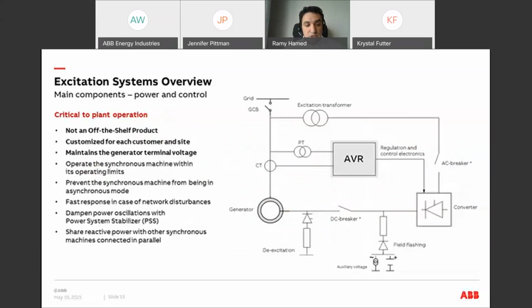So after we've been through the main functions of the excitation system, now we move to talk about the main components of the excitation system. So in this single line diagram, we have here the generator. This is the generator stator, and this is the generator rotor. As we explained before, the excitation system will supply the rotor with DC current. However, since normally all the supplies are AC, the first component needed in the excitation system is the converter to convert AC to DC.